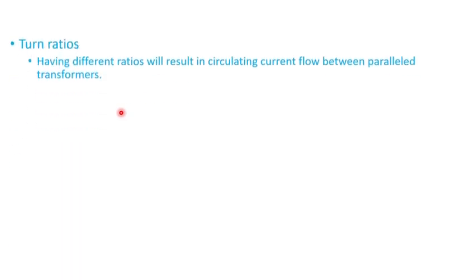So having different ratios, turn ratios, will result in circulating current flow between the parallel transformers. That's very important to remember when you have two transformers that are in parallel, whether they have a load tap changer or de-energized tap changer. It's important to have those transformers with the same turn ratio.